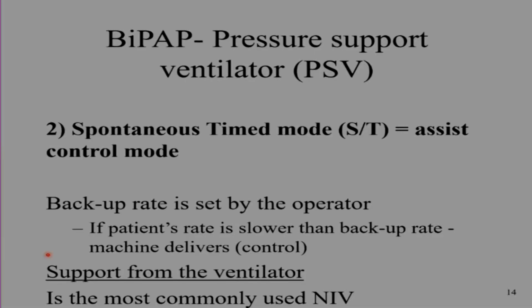The second type is the spontaneous-time mode. It has the spontaneous mode, supporting the breathing every time the patient breathes, but it also has a backup rate set by the operator. So if the breathing rate goes below the backup rate, say 8 or 10, the machine starts to pump air and overtakes the patient's breathing, controlling it. This is the spontaneous-time, or ST mode, and it is safer.